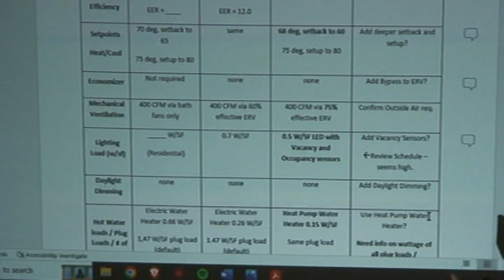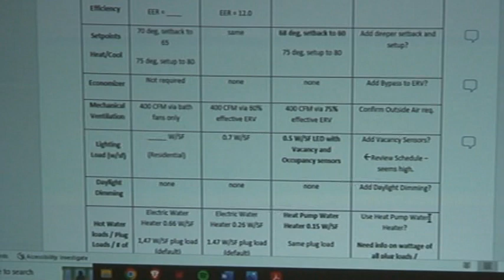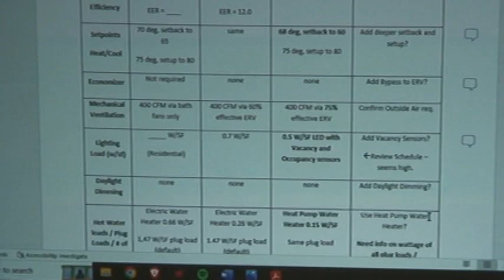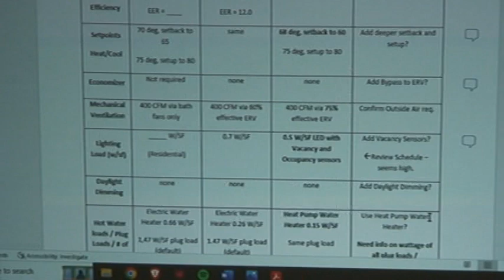For lighting load, I have to plug in how much lighting load there is in there. I've got 0.7 watts per square foot in the first case, 0.5 with LED and vacancy sensors or occupancy sensors in the better version. I don't have any daylight dimming. If you have a lot of glass, you can actually dim the lights up and down based on how much incoming sunlight you have. I don't have that in the model here. Is that not required by this code? It's not required by the code unless you have too much glass. If you have too much glass, more than 30%, then you're required by code to do it.